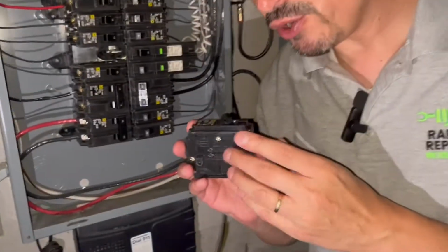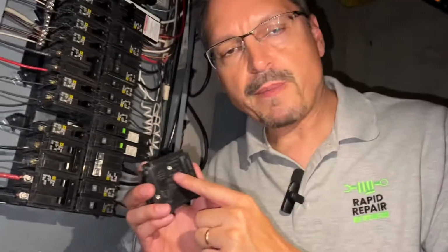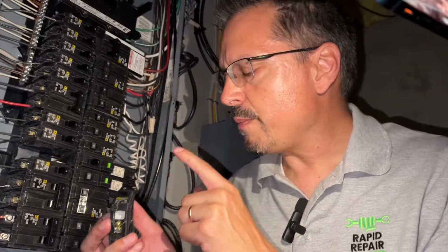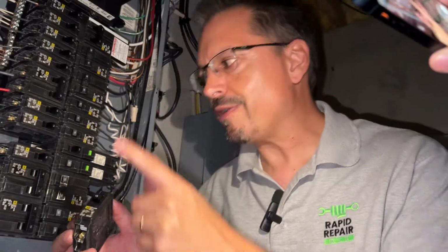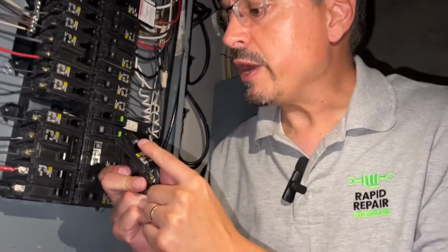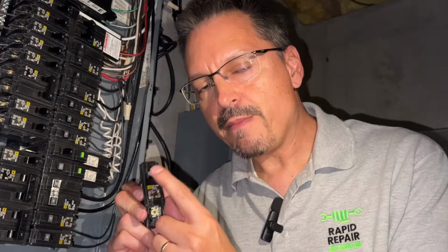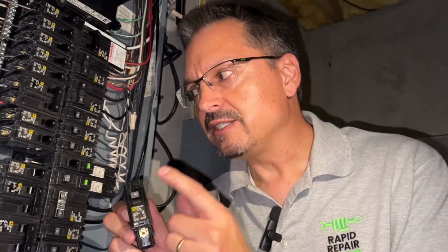Now, when you guys buy your new circuit breaker, all the needed information is at the side. You do want to buy the same manufactured circuit breaker as the panel. That has to match. You want to buy the same amperage size. Right here it says 15 amps. There's also 20, there's 30, there's 40, there's 50. You want to buy the same matching amperage size as the existing breaker. You don't want to go larger on that.